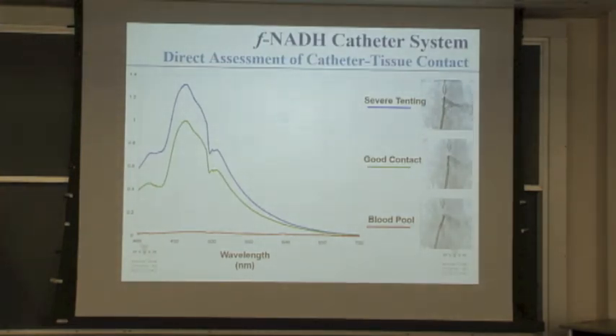This is the catheter not touching tissue, and pushing, touching and really pushing hard against the tissue. So when the catheter is not touching tissue, it's just sitting in blood, and there's no NADH in the blood to be able to visualize. As it touches tissue, you see this peak at 450, well, 460, whatever. How do you use that? Well, this is what happens during ablation. In addition to knowing you have contact, as you ablate, the NADH signature basically decreases. And here you're seeing this decrease, and here you're actually seeing a decrease in real time. This is over the course of 10, 15 seconds, whatever.